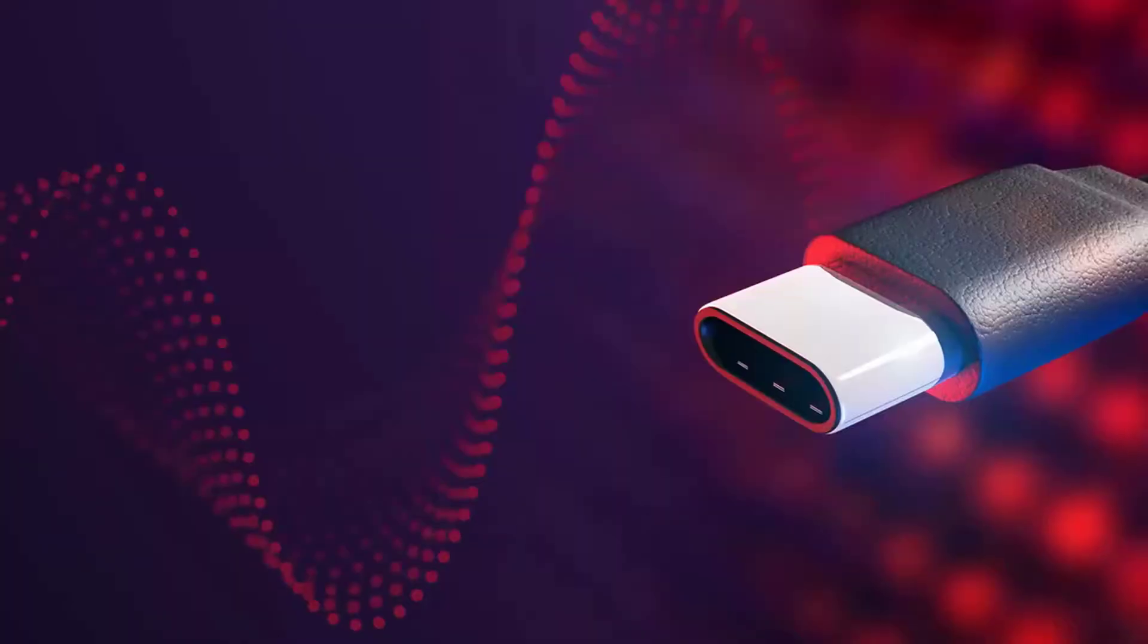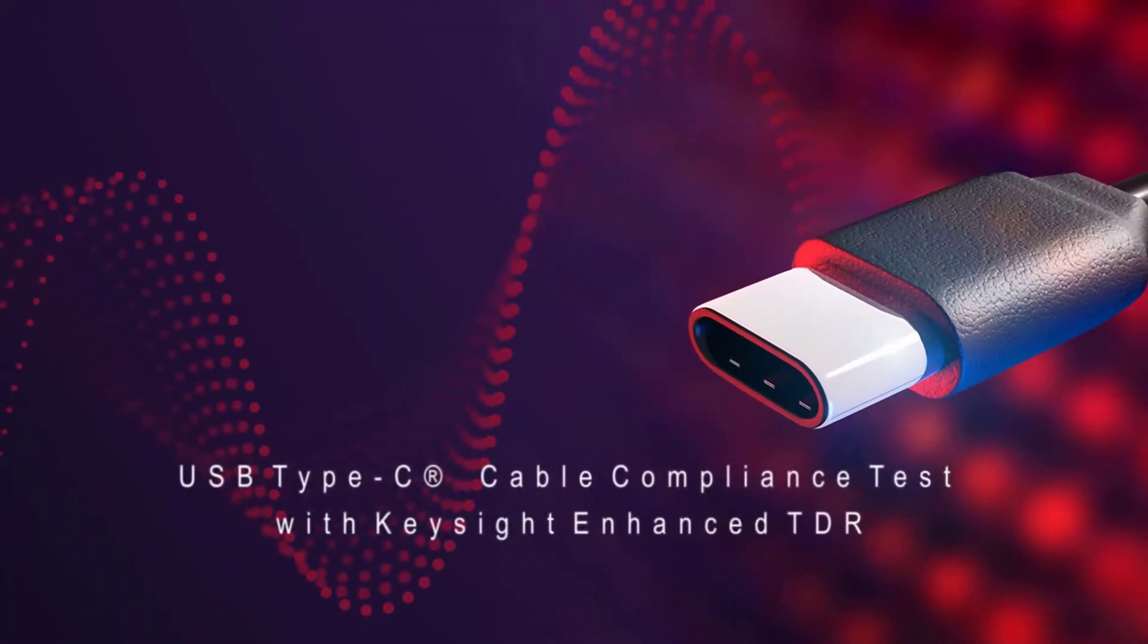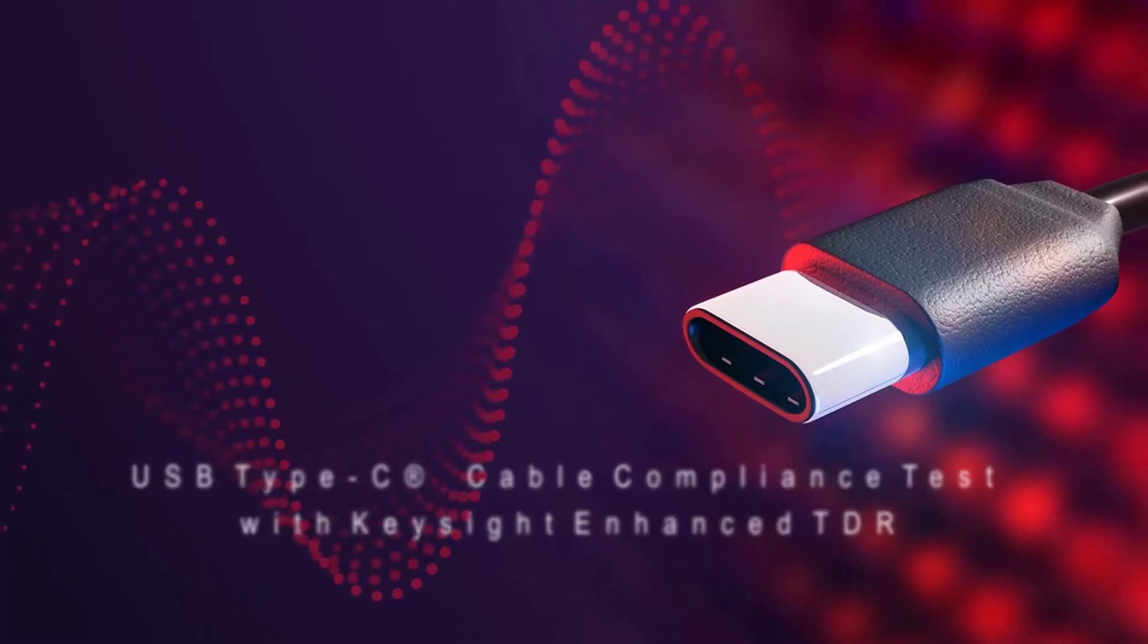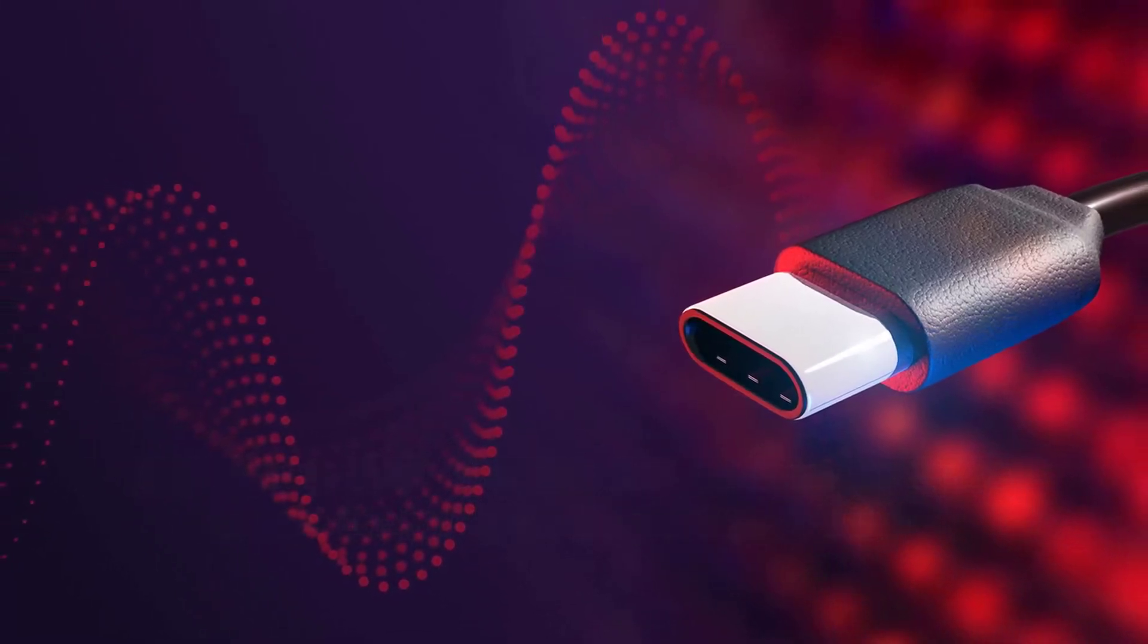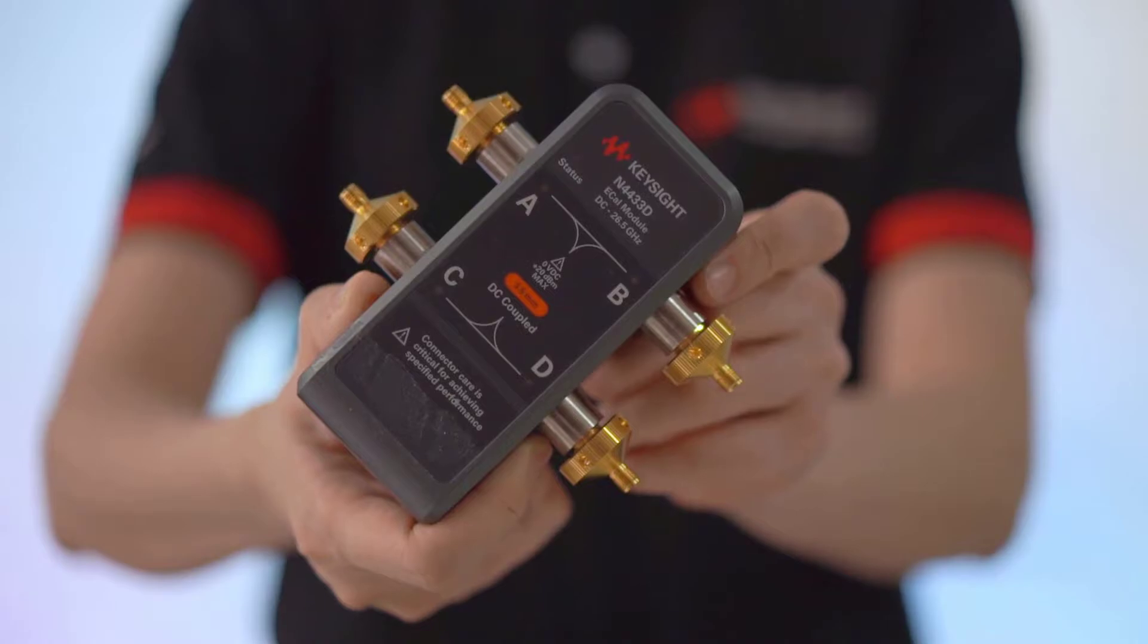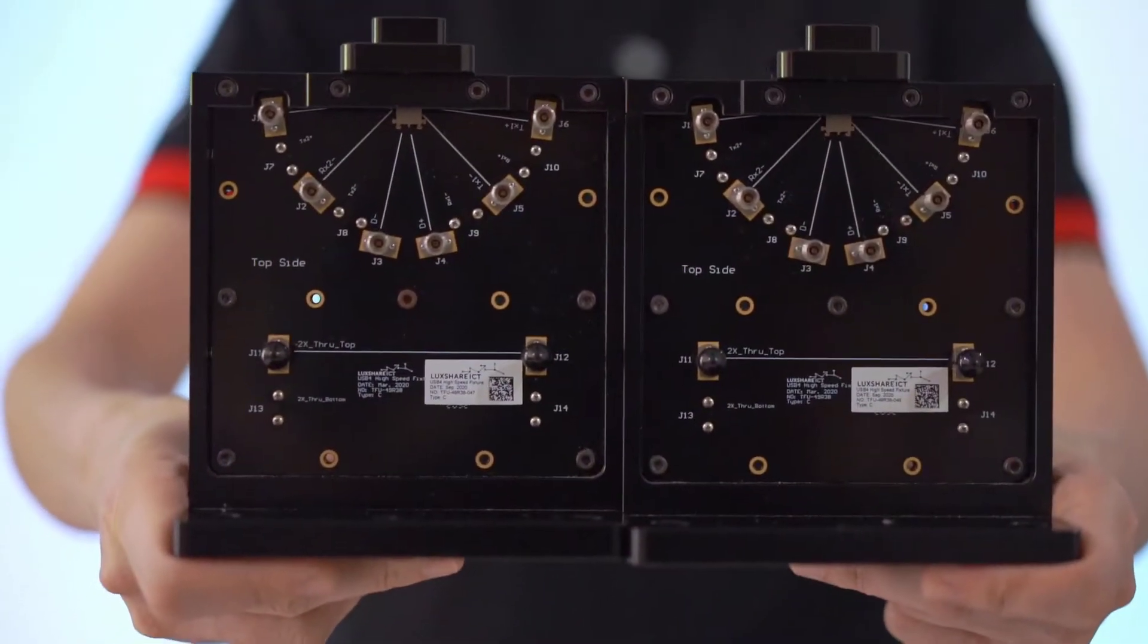In this video, we'll show you how Enhanced TDR application helps simplify the test process for USB Type-C cable compliance testing. The main setup in this demo, aside from a Keysight VNA with Enhanced TDR software, are a 4-port ECAL module, USB Type-C test fixture, and a USB 4 Type-C plug-to-plug cable as our device under test.